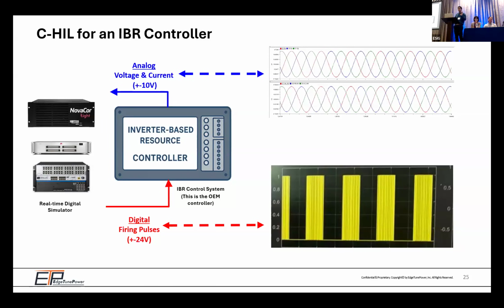The purpose is to show that this methodology of hardware in the loop testing is important, where you can connect the controller to the real-time simulator. For example, if it's an inverter-based controller, you can send analog voltage or current signals to the real-time simulator and the switching pulses back to the control system of the inverter, which is under test.